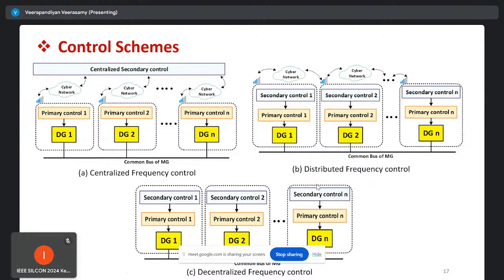In case of tight control of a system, if we need to maintain consensus, we opt for distributed control. Centralized control may lead to failure—if the centralized controller fails, the entire system may not operate. Whereas with distributed control, if one controller fails, the system is still more reliable to supply. So distributed control gives more reliability, but it is prone to cyber attacks due to the large number of communication lines between controllers.